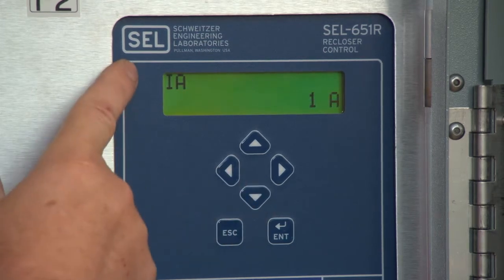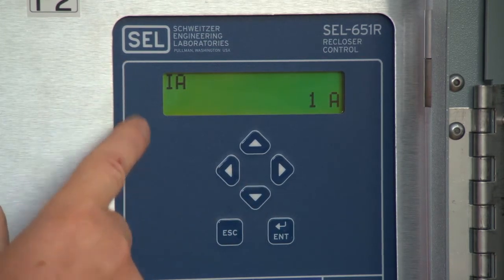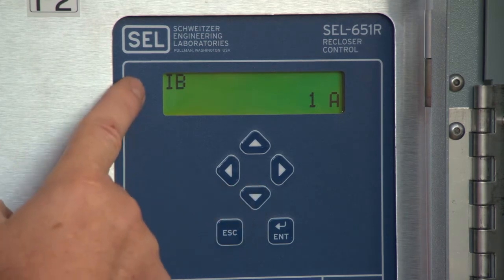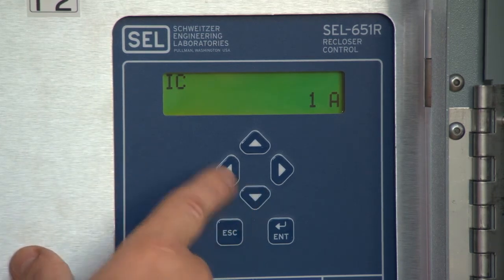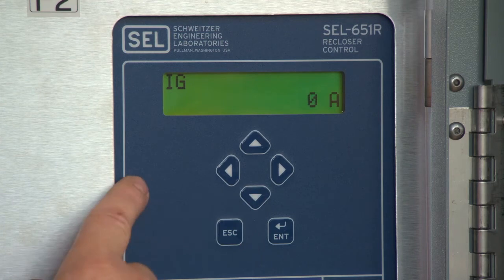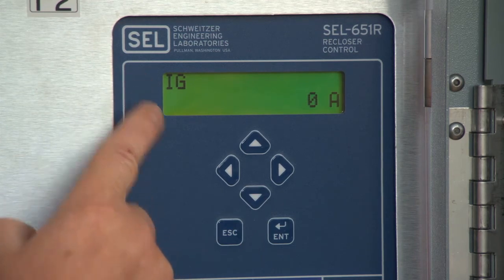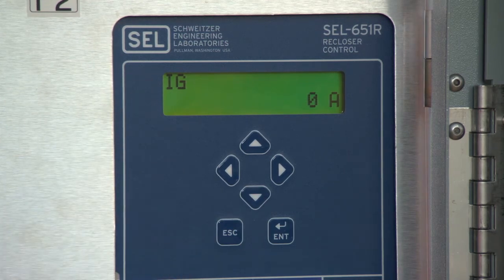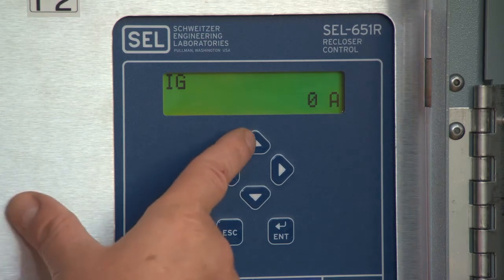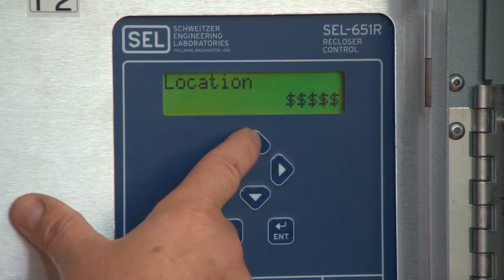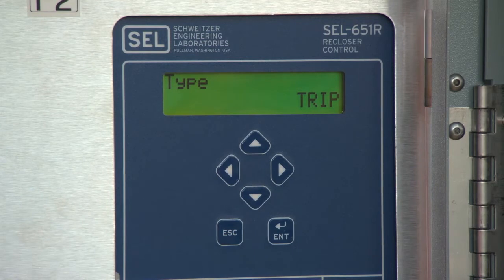Pressing the down arrow key will display the A-phase current and according fault condition if it exists. Then the B-phase current and according fault. Next, the C-phase and according fault. And G or ground current and according fault. In the case of this example, it was not a fault condition but rather a manual trip by us. No amperage was displayed in the screen. Press the Escape button to return to the main scrolling screen.